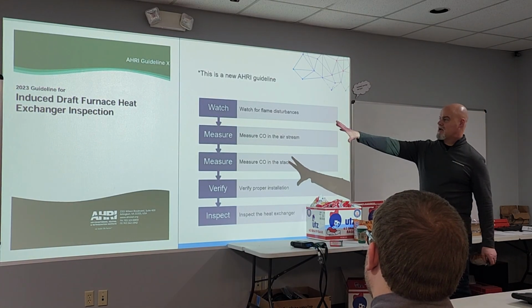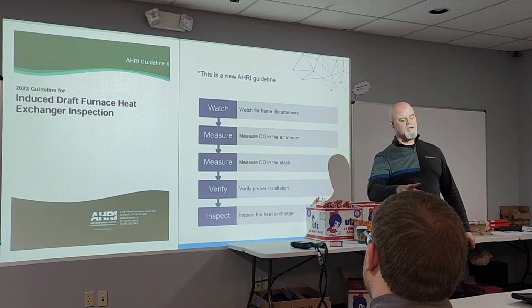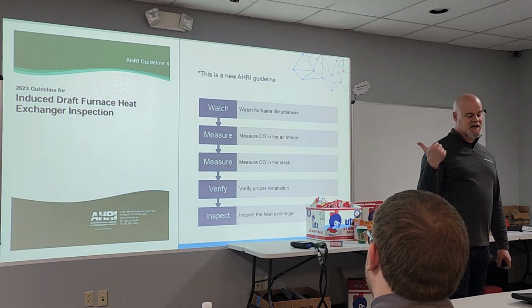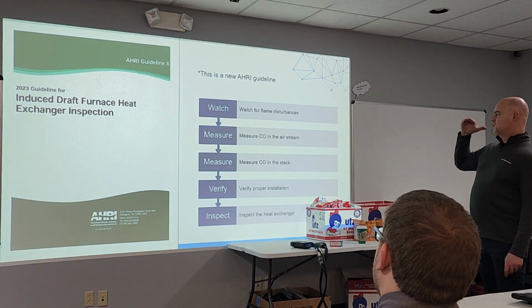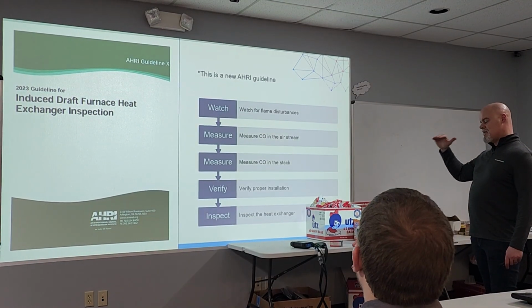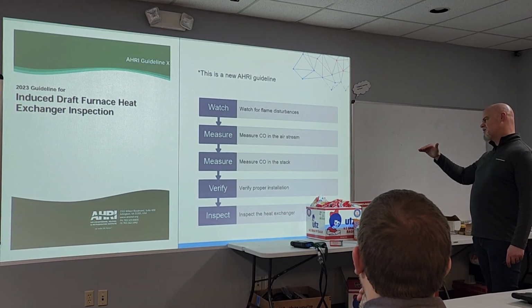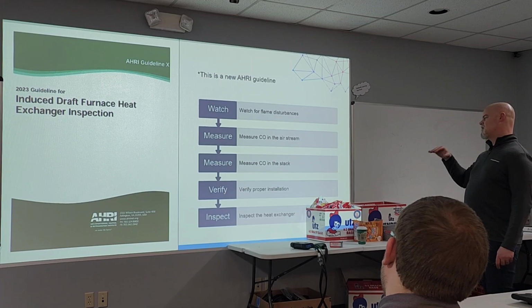Here we go, AHRI Guideline X, not only me telling you you have to use a combustion analyzer, but they tell you it's actually part of the specification. So watch for flame disturbances, measure CO in the airstream, measure it in the stack, verify installation, inspect the heat exchanger.